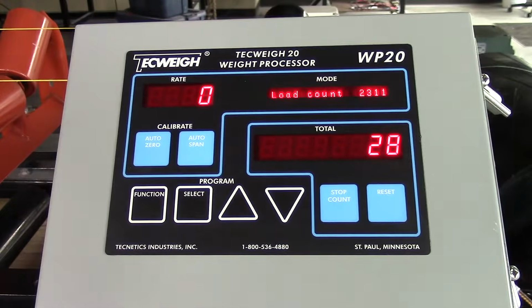Now let's look at the load counts. That's the value you see whenever you actually put load on the conveyor. We'll add some calibration weights to the belt scale, and you can see that go up. You can see the load counts rise, and you also see the rate go up as well.